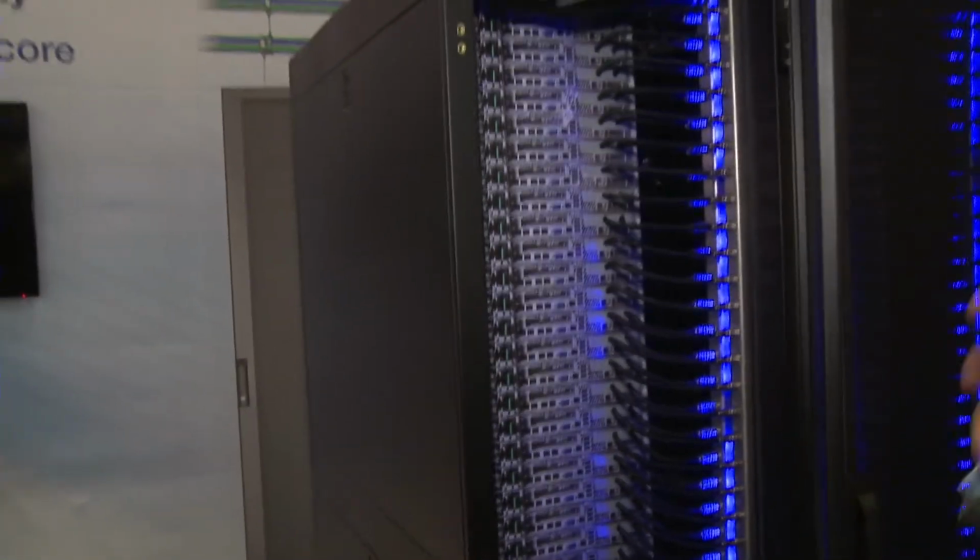That's exactly right. It sounds like an awful lot of flow still, with 350 liters a minute, but it is governed by pressure. As you look at these types of systems, it's highly parallel. Each of these main feeds is supplying 42 here, 42 here, 42 here. It ends up being a very highly parallelized system, and we end up with very low pressure drop. So it's a very comfortable and, we believe, very reliable system.